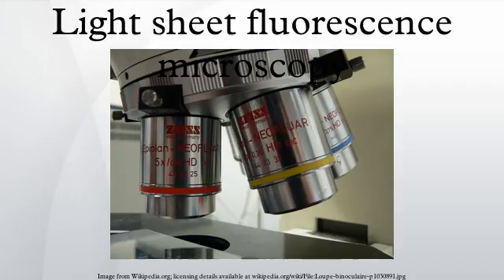The fluorescence light emitted from the light sheet is collected perpendicularly with a standard microscope objective and projected onto an imaging sensor. In most LSFMs, the detection objective and sometimes also the excitation objective are fully immersed in the sample buffer, so the sample and excitation/detection optics are embedded in a buffer-filled sample chamber, which can also control environmental conditions during measurement. Focusing different parts of the sample cannot be done by translating the detection objective; instead, the whole sample is translated and rotated.